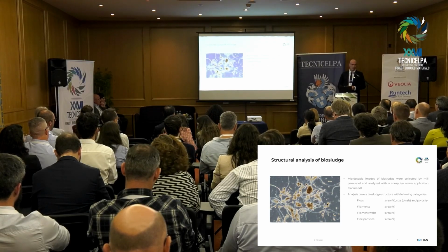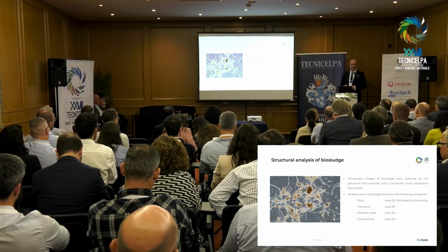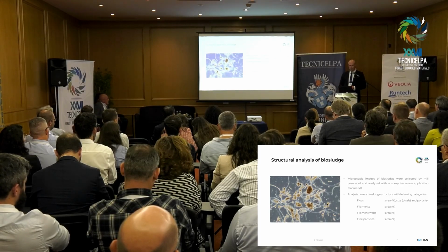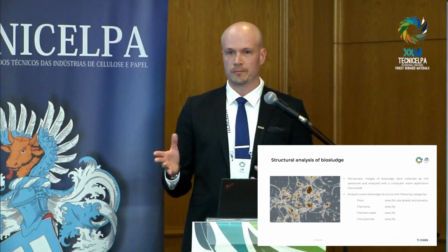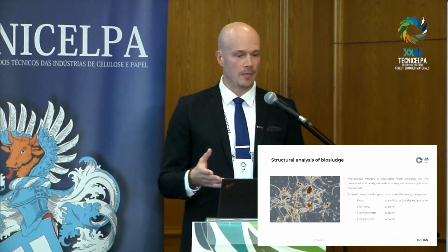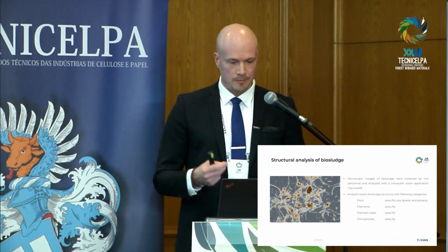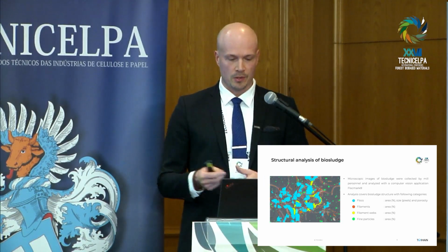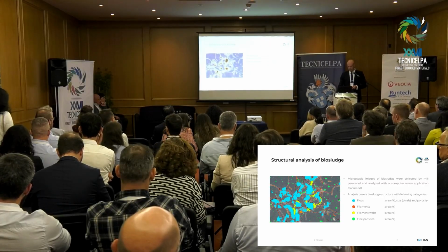It's an image analysis, so it's big pixel analysis, of course. So from flocs, we get floc size, floc porosity, floc density; from filaments, the area, the amount of biomass that were filaments. We also have filament webs if they are forming webs, and fine particles that we see.